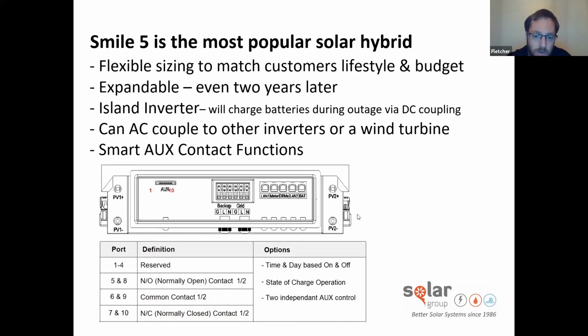As you can see here on the screen, your options are time and day based on and off. But the more interesting one is the SOC, or state of charge operation. This means you can decide that as soon as the batteries are full, you activate something, and it remains active until the batteries drop down to a certain percent, roughly around 80%. That's a very good function.